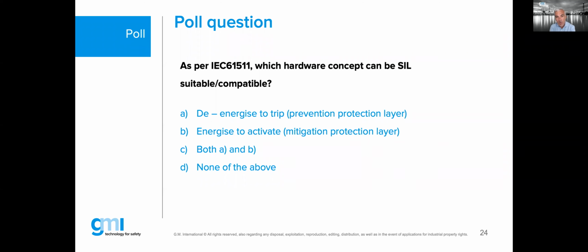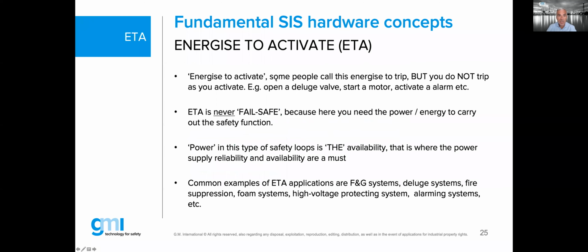All right, well, we do have 78%, which is a big chunk of, let's say, the majority here, saying it can be applicable for both A and B, which, you are right, is the most correct and the most complete answer. Those who are thinking it's only applicable for de-energized to trip, well, that's only 22%. That's, let's say, the most common misunderstanding of edition 1 of the standard. That's why edition 2 has made some new statements, which I also made a copy here in the slides. So it's coming from technical report number 4, but I will show that in a minute. And of course, both A and B is the most correct and the most complete answer. All right, let me just continue.